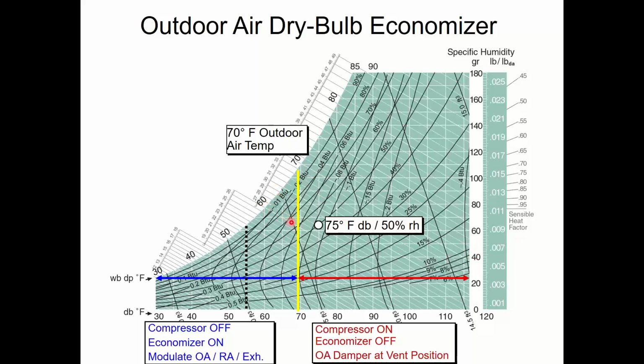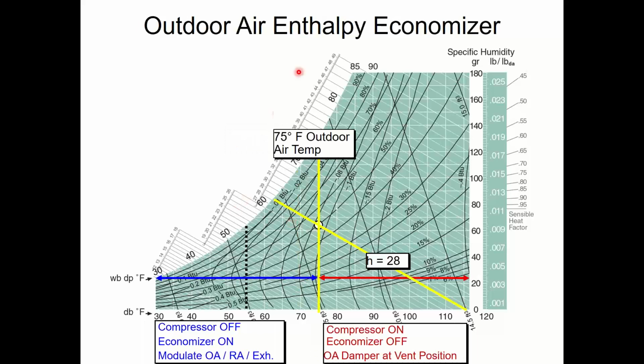And the way we're going to do that is by using enthalpy. So if you don't know on the psych chart, these little tiny lines over here, those little numbers that you can barely see probably, those are enthalpy numbers. It's basically temperature and humidity combined, which is why the line is on an angle. All these white lines on an angle are enthalpy numbers because it involves the moisture and it involves the temperature.